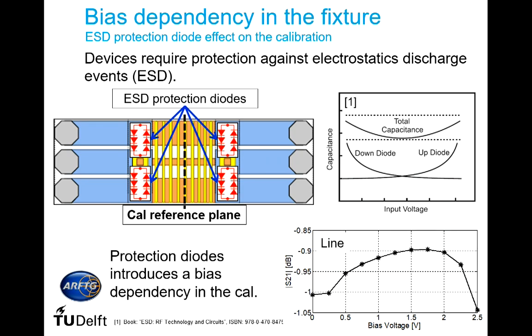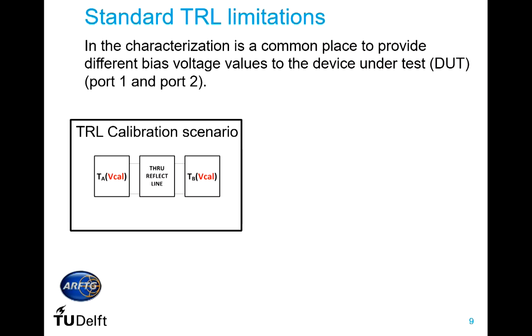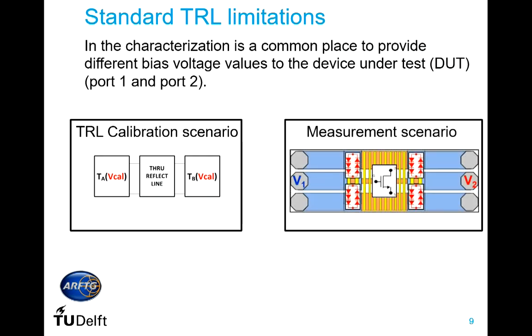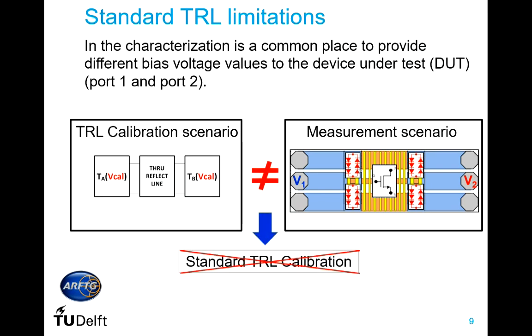This variation is not something we expect because the line is a passive structure. That means this variation comes from an error in the calibration. When we perform the TRL calibration, the TRL uses as standards: thru, reflect, and line. We have to apply the same voltage at both ports — usually zero. We can apply a different bias using an open as reflect, but in the typical measurement scenario we characterize our device using different bias on port one and port two. That means the measurement scenario does not match the calibration scenario, and we cannot use a standard TRL as calibration.